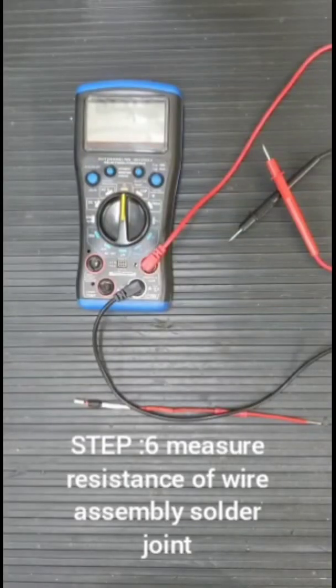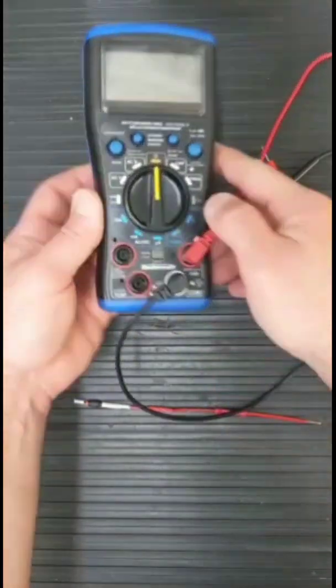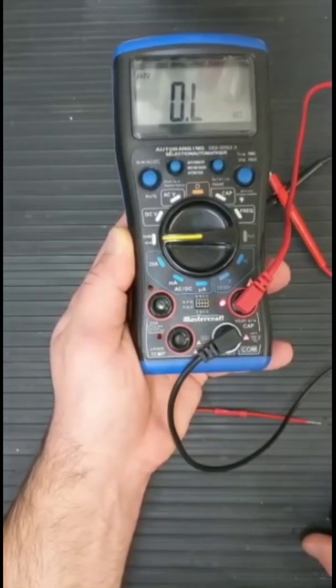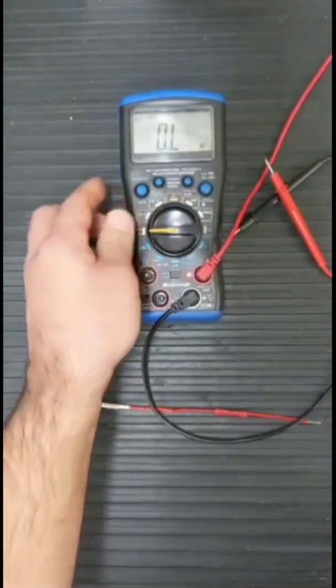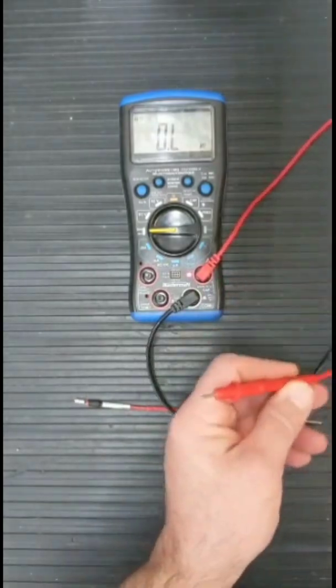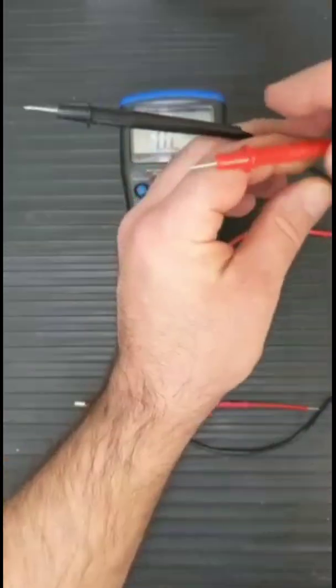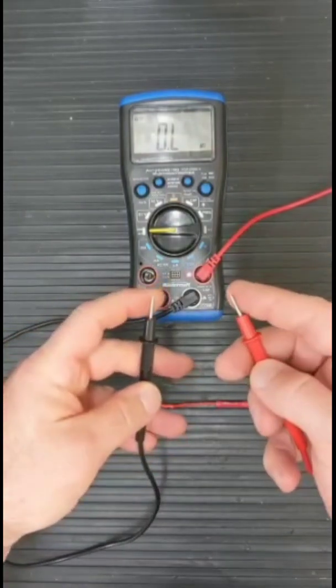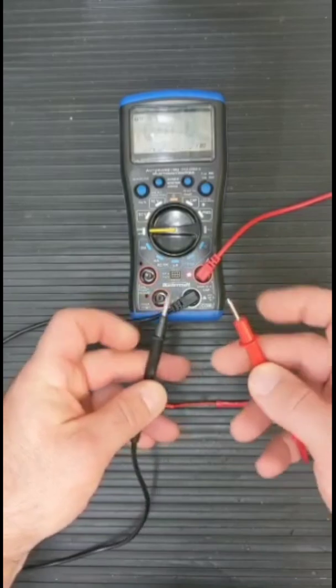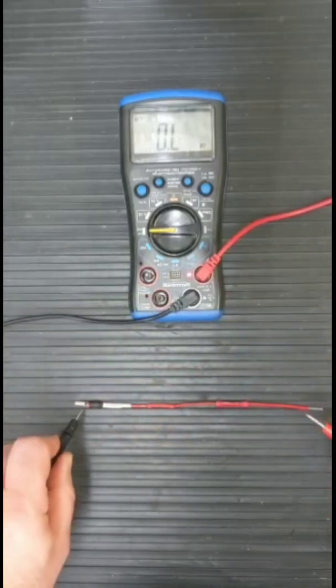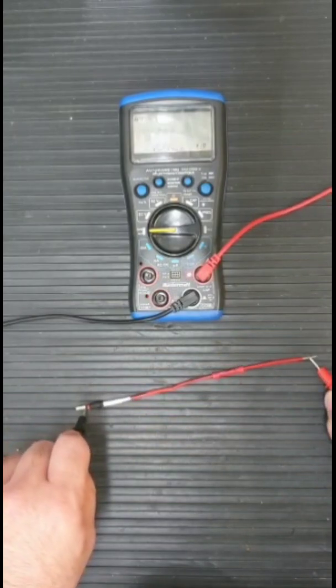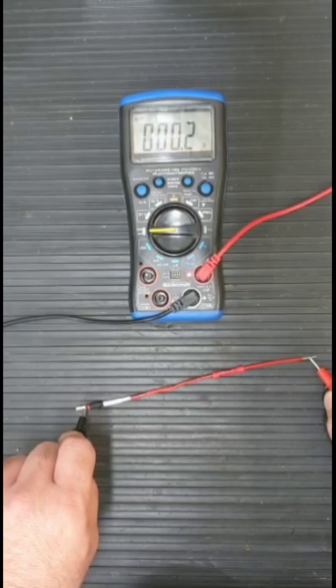We'll now be measuring the resistance of the wire assembly. You want to make sure your meter is set to ohms. Two things you want to make sure of: your wires are not crossed when you're testing resistance, you want to make sure they're both separate. You also don't want to touch the ends with your skin, so make sure your fingers are away from the end of the probes. You're just going to touch one end of the assembly as well as the other end, and you should get a result of less than one ohm.